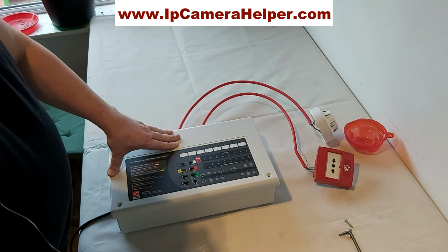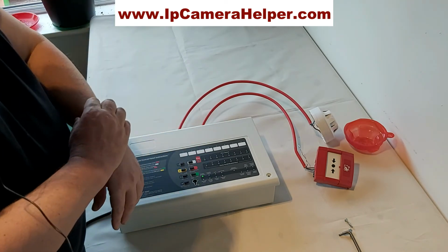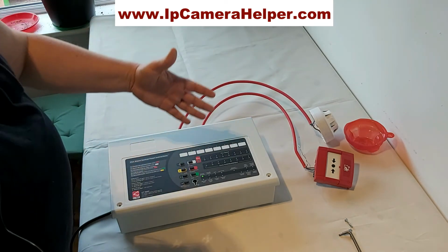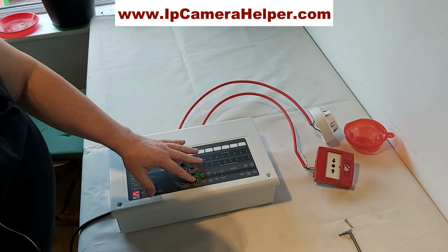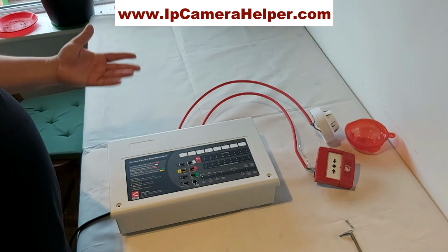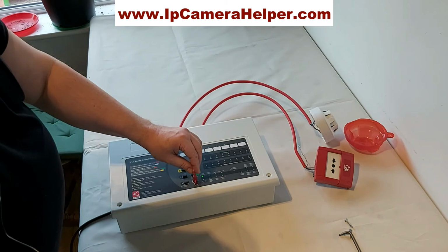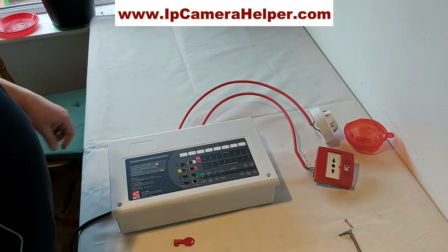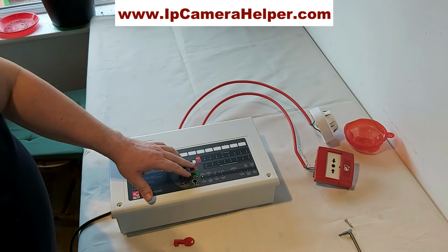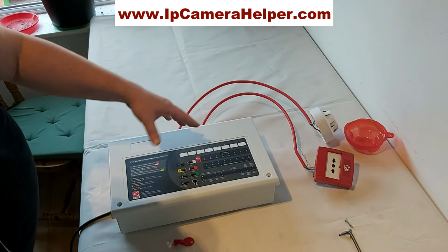Basically these are the most common things you can do with a fire panel, more or less any fire panel, but in general the easiest thing is to work with conventional fire panels. From the user point of view, it will be the same, conventional or non-conventional. Usually you have those 3 buttons: silence the beeper, silence external sounders, and reset the panel. And some sort of access, either an access code to reset the fire, or the key, or sometimes there's nothing required to access those controls. It may not let you, for instance, reset the panel, but may let you just silence the sounders or something like that, or see what's happening.